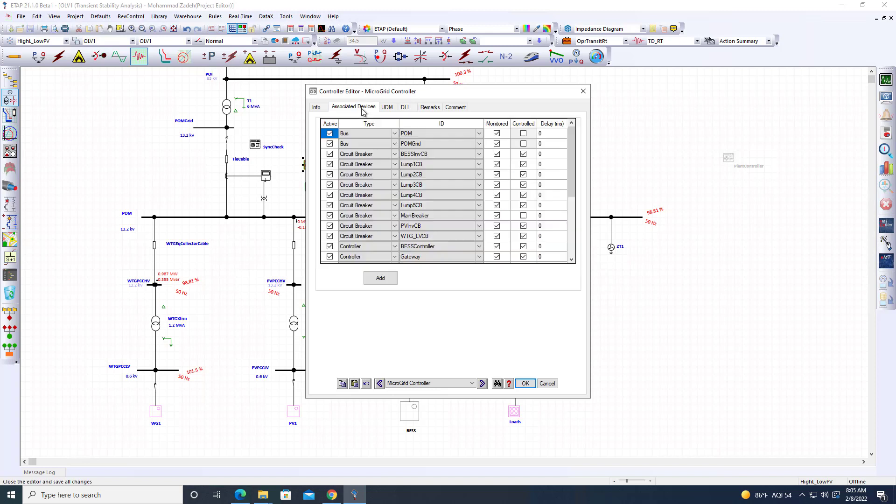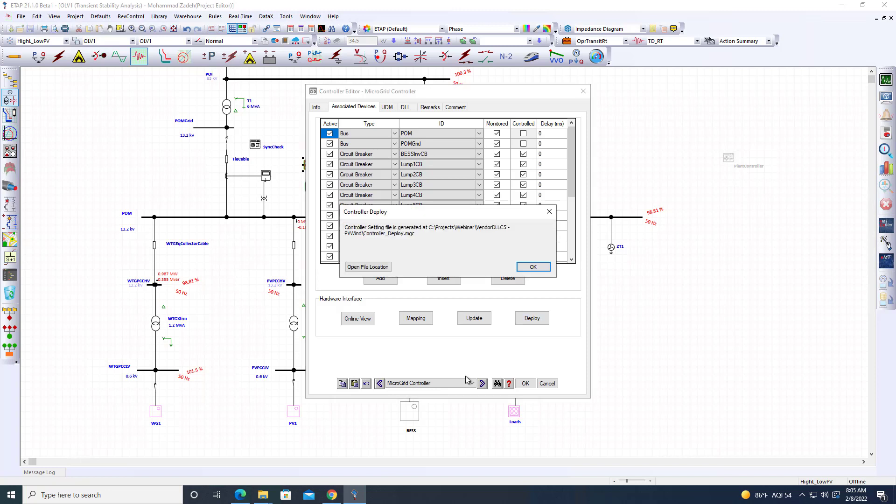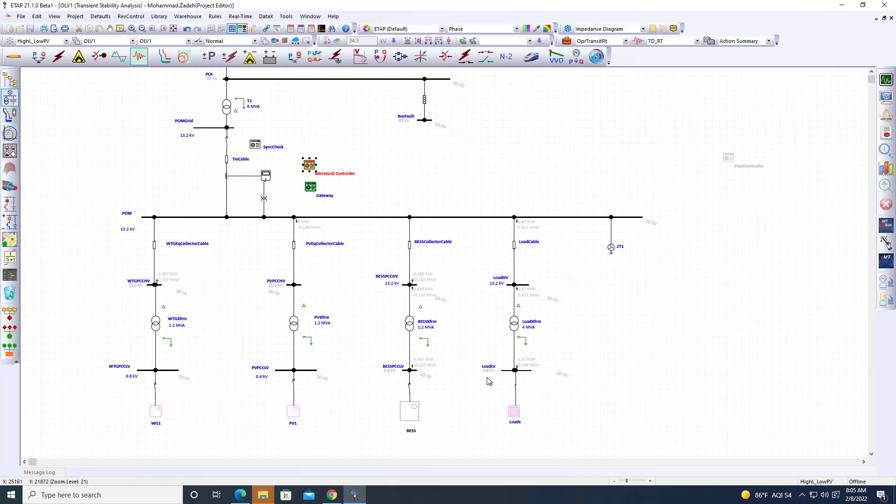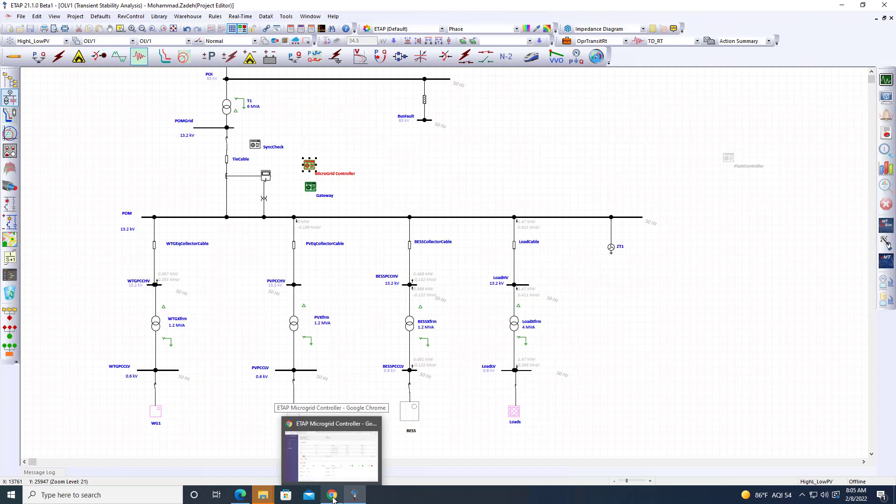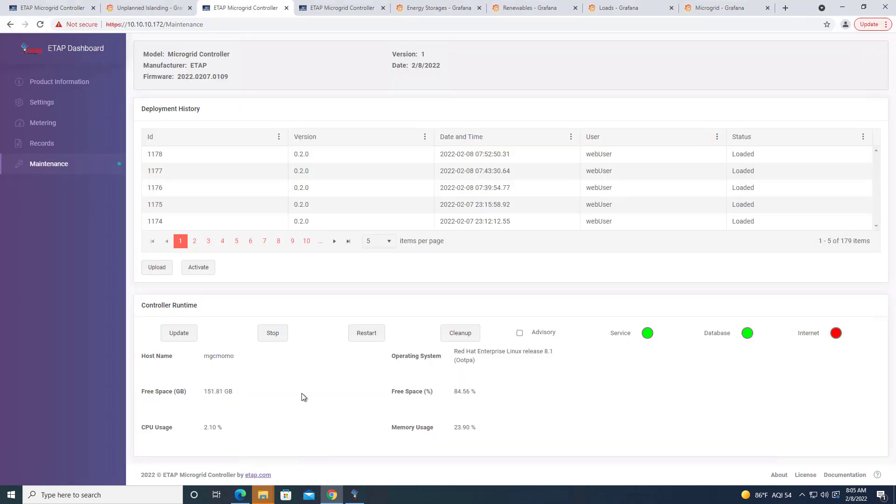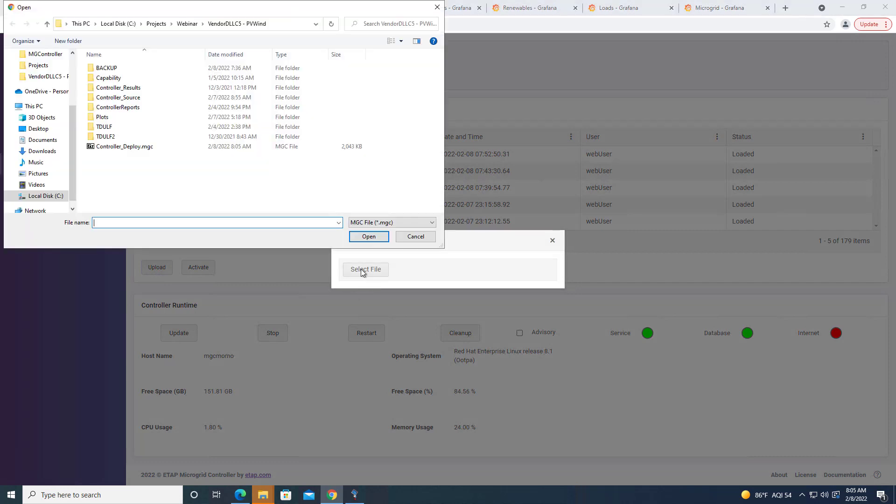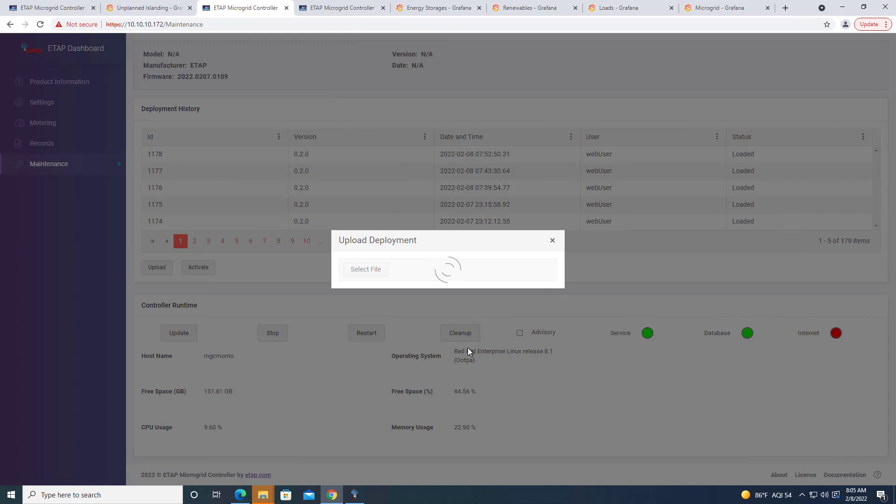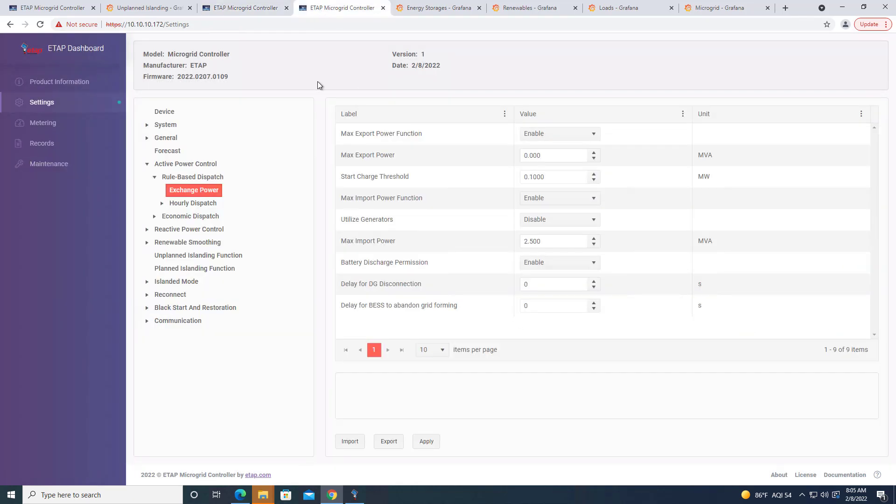The first thing we're going to do is deploy. What the deploy does is it creates a package, which is an MGC file. It creates a package of all the logics, which are a DLL of the digital twin, plus all the settings, the connectivity, the network information, and puts them in a package. We can go ahead and upload that into our microgrid controller. We say upload. So all the logic settings, everything is now uploaded into the box in a few seconds. Done.